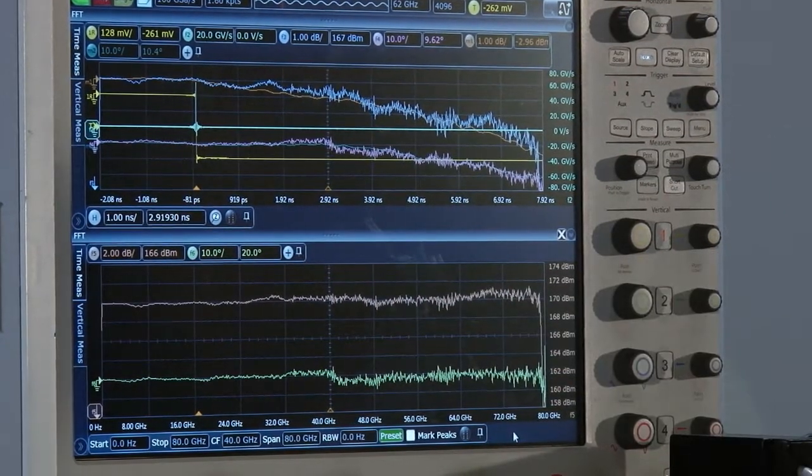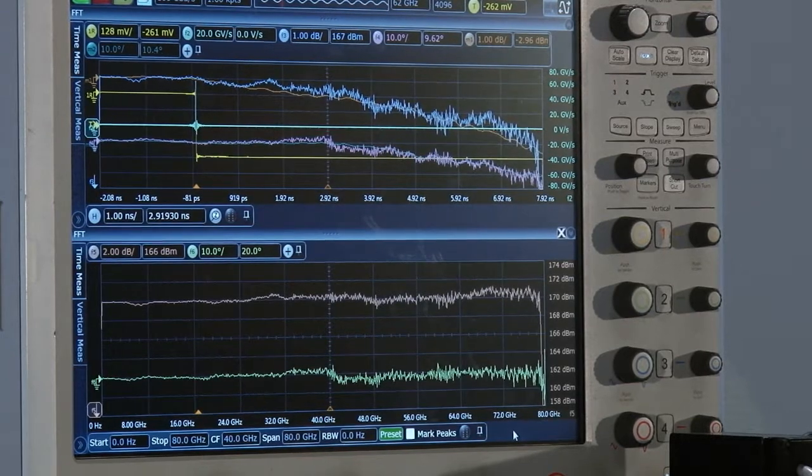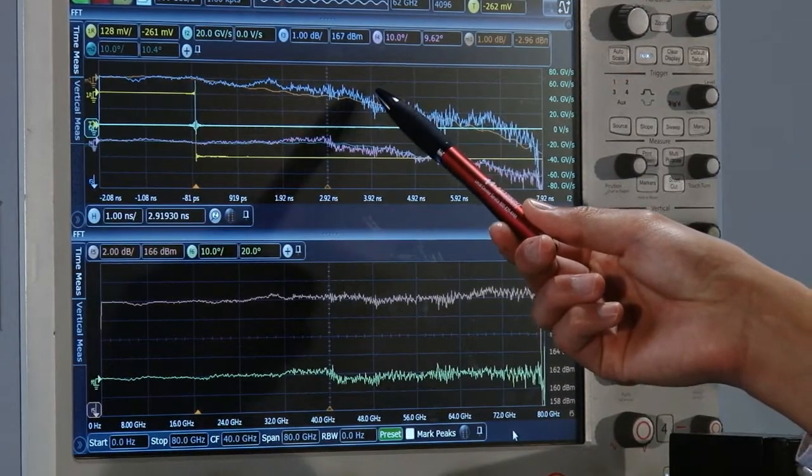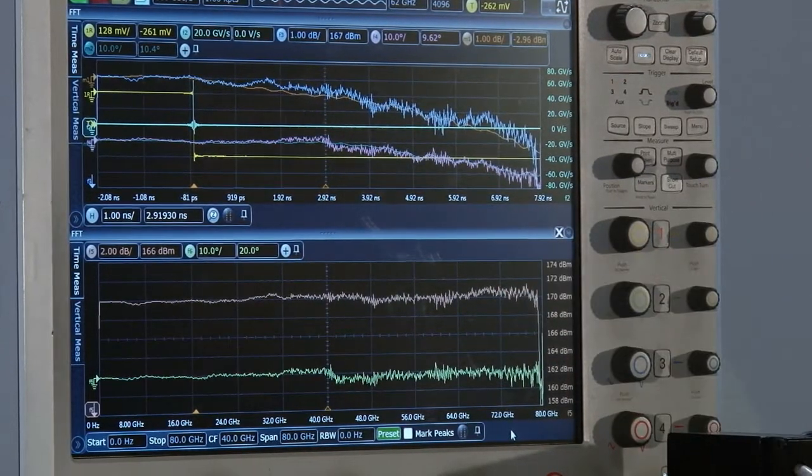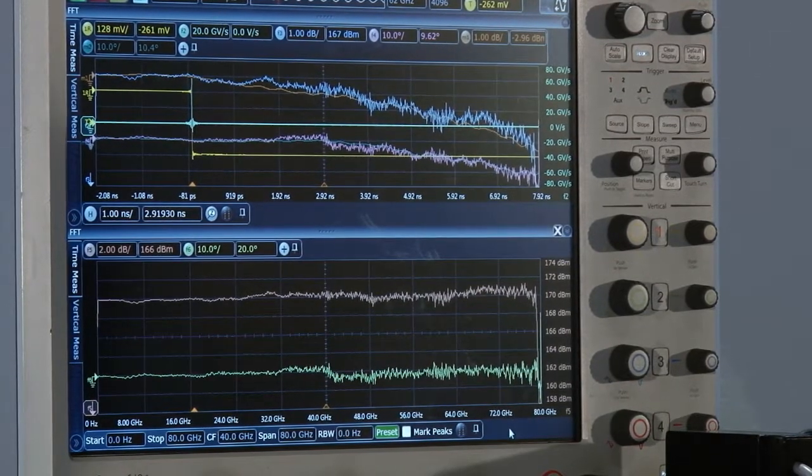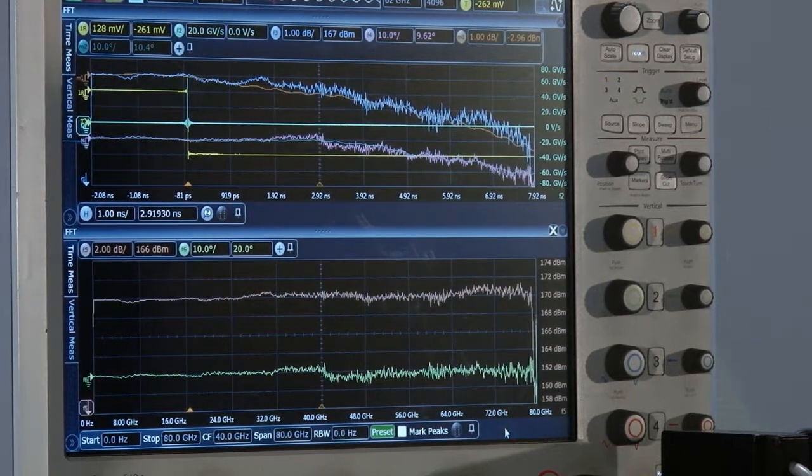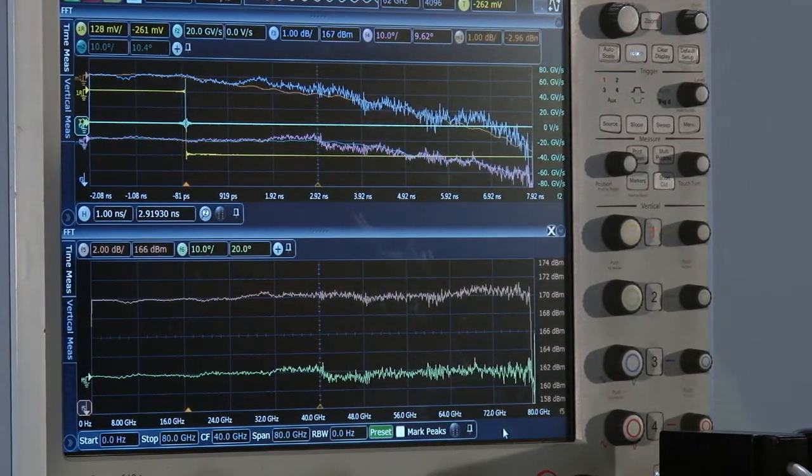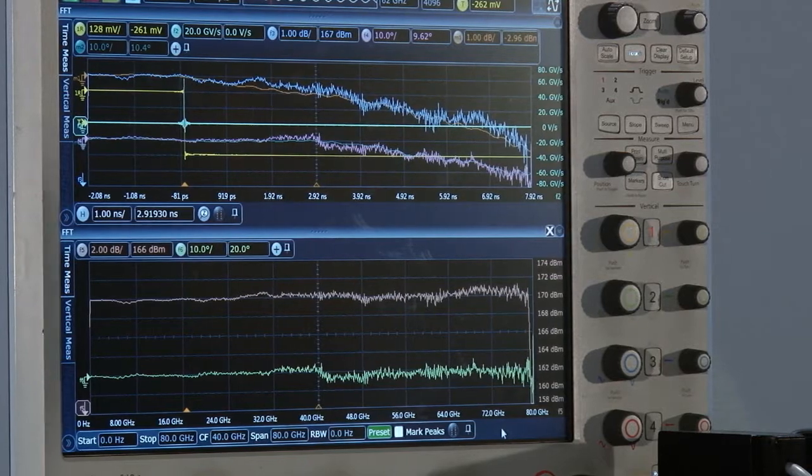And then we will perform the FFT magnitude and phase measurements, as you can see on the blue and the purple waveform. This step generator is calibrated towards the NIST photodiode for traceability. And we have characterized the error of the step response as well.